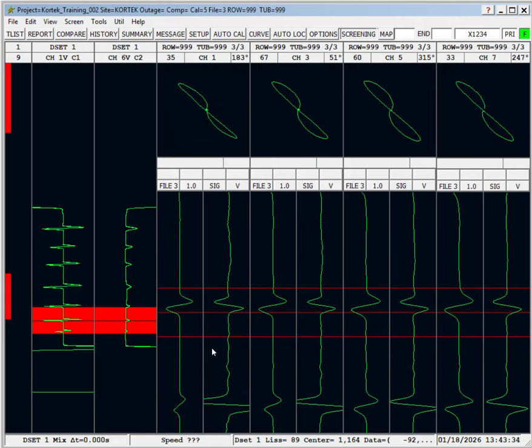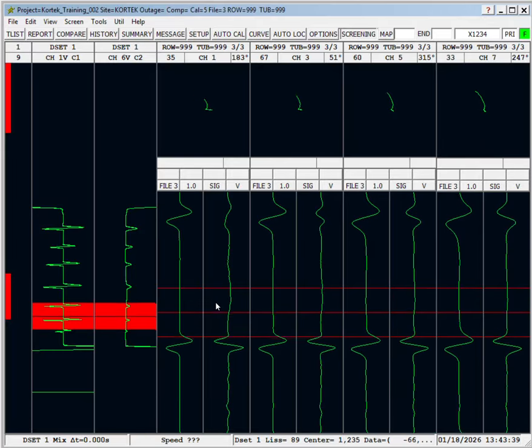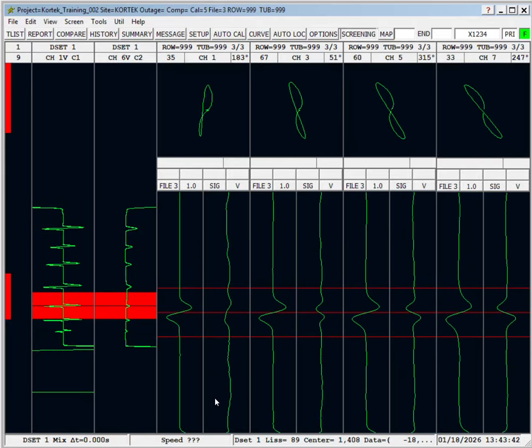But just a little recap on phase analysis. If you set the 100% hole to 40 degrees on all of your raw differential channels, notice what happens to the phase as we get to an 80% flaw. They rotate counterclockwise as you decrease in the frequencies. So for example, this 80% hole is at 94 degrees on channel 1. It rotates counterclockwise on the next lowest frequency. It goes from 94 degrees to 69. If you lower your frequency even more to channel 5, you're going to have more counterclockwise rotation with decreasing test frequency. So this rotates just as an OD flaw should.